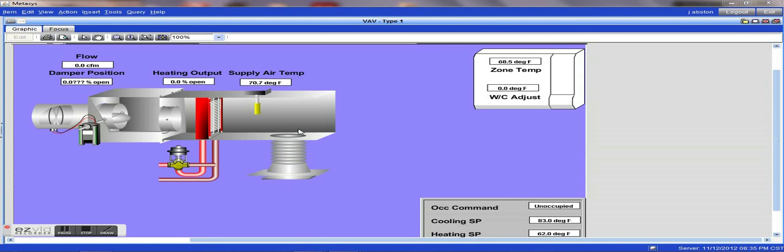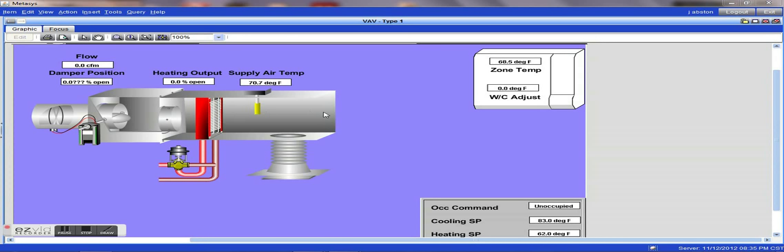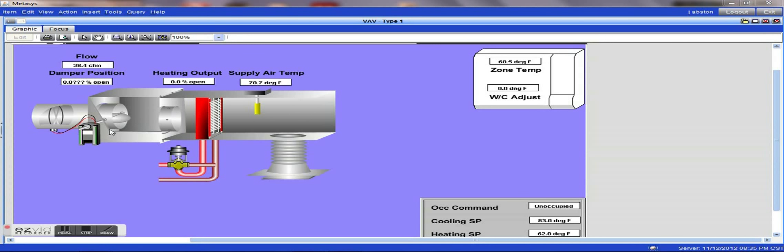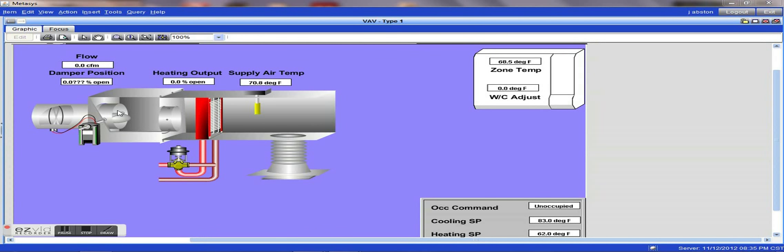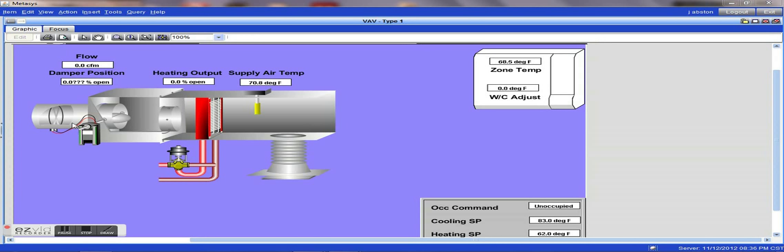One thing you will notice when air flow is adequate in the room, whenever it is at set point, is that it will usually go to a minimum value, a minimum flow set point. Generally, when you are trying to cool a space, you will have more air flow into the space through the VAV, opening the dampers, allowing more flow.